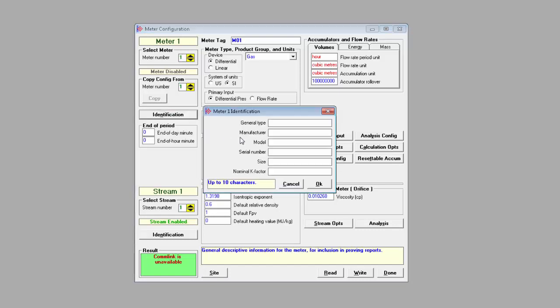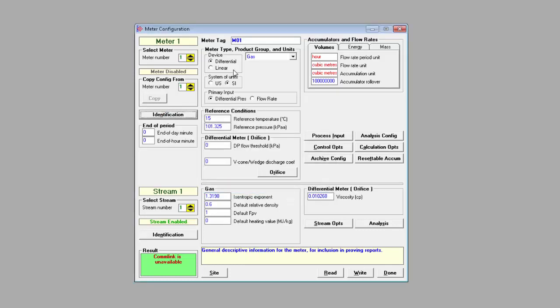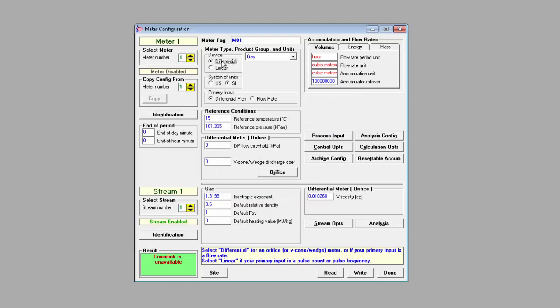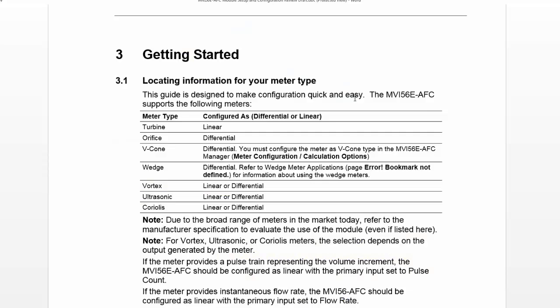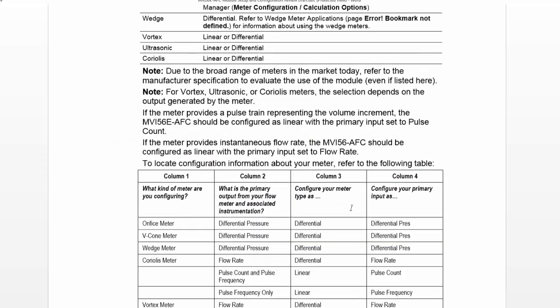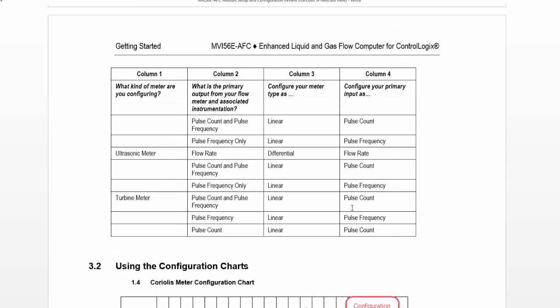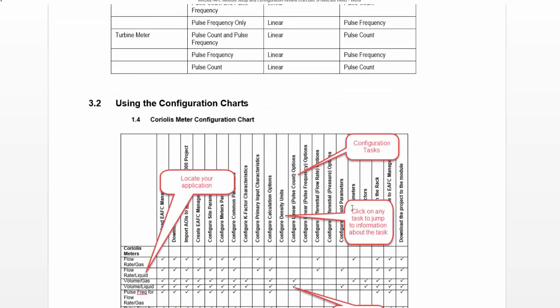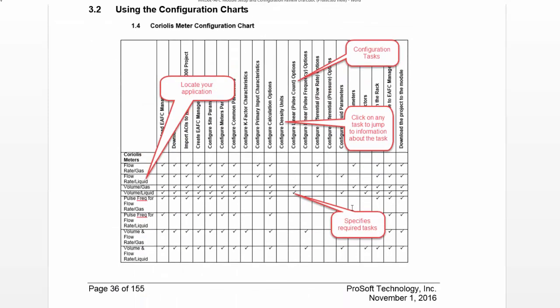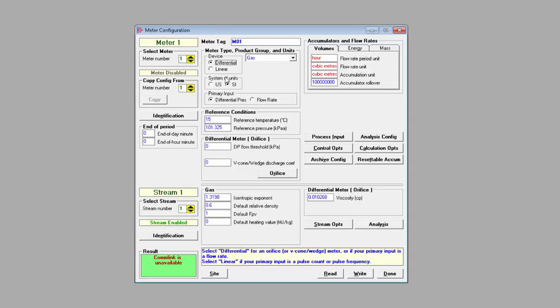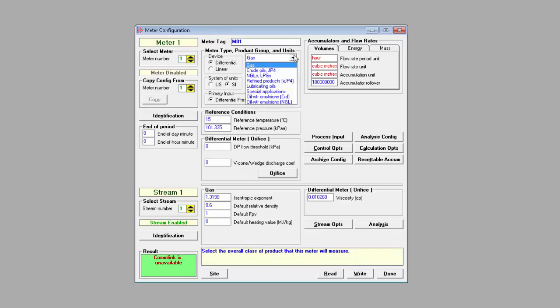By clicking on Meter Identification, you can enter in all pertinent information for your various meters. Under Meter Type, you can select Differential and Linear. Essentially, if you choose Differential, you're choosing the AGA-3 standard, and if you select Linear, you're choosing the AGA-7. For the broad range of other meters available today, your selections will depend on the output generated by the meter. Refer to your meter's specs and section 1.1 of the MVI56E AFC Module Setup and Configuration Guide for more information. For meter 1, I'll choose Differential. And for meter 4, I'll choose Linear.